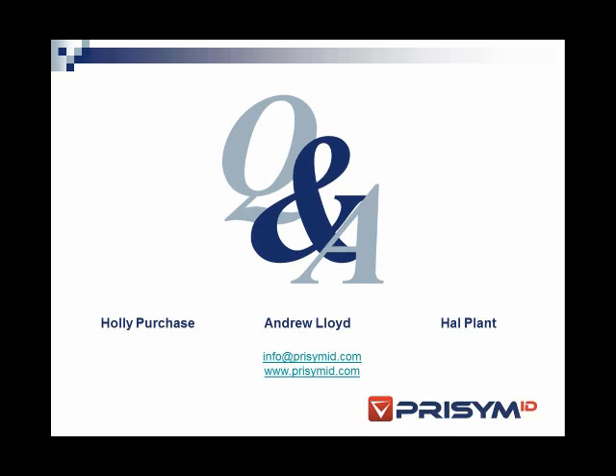Okay, let's try Hal probably for the next question that's come in. The question is, if we're implementing a solution such as this, where does the FDA compliance sit? Is it with us, or is it with the solution provider? Certainly with the customer. Based on the projects we've worked on, we can offer a great deal of best practices and suggestions, but at the end of the day, it's going to be you, the customer, that needs to present what you're doing and prove what you have done to the FDA. So we can certainly help, but at the end of the day, it's the customer that needs to stand up to the FDA.